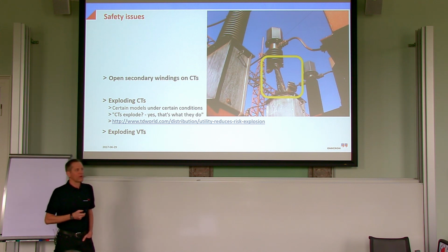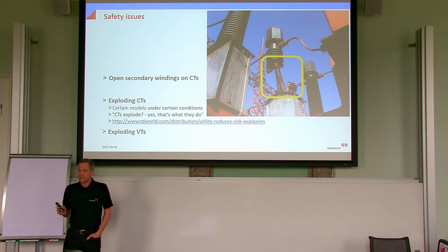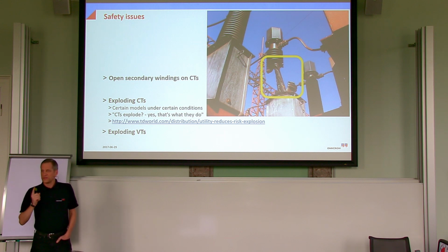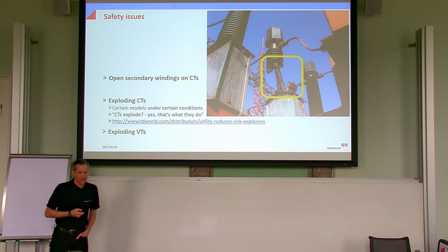And 2 years ago, I was at the Transformer conference in Australia, and I touched the topic a little bit and asked the people if they know about exploding CTs. And one person who has been in this transformer topic for a long time was absolutely not surprised by me asking that. She said, if CTs explode, yes, that's what they do.